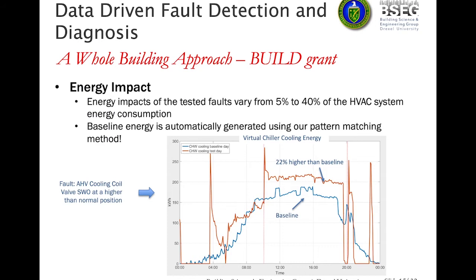One added benefit of using such a data-driven approach is the ease of identifying the energy impact or other performance impact coming from the AFDD strategy. Again, because we assemble a baseline that is automatically learned from historically collected data under similar weather and operating conditions, when the incoming snapshot data comes in, you can very easily see the energy impact or other performance index changes.